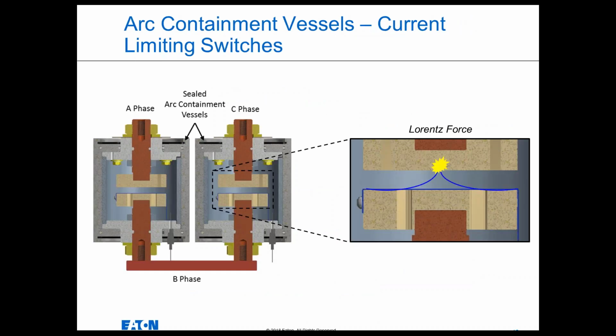So I know that still doesn't really get to the meat of the issue, and that is: how does the arc quenching device actually create that lower impedance fault? This is probably my favorite thing to talk about here. This is what's inside the arc quenching device. There are actually two arc containment vessels. What's shown here are cutaways. They kind of look like vacuum bottles, VI bottles, but they're not.